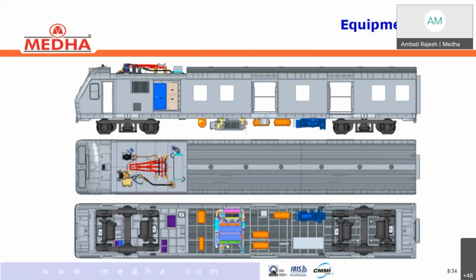So during maintenance, you have to remember how you are opening the connection; in the same way, you have to connect it again exactly. Because we have given connection to this motor as UVW, and here one phase is swapped for number 2 and number 4 motors, as they are physically placed reverse to number 1 and 3 motors. That is the reason the electrical supply is also given in reverse, right?